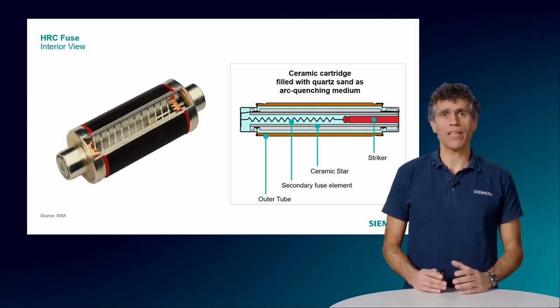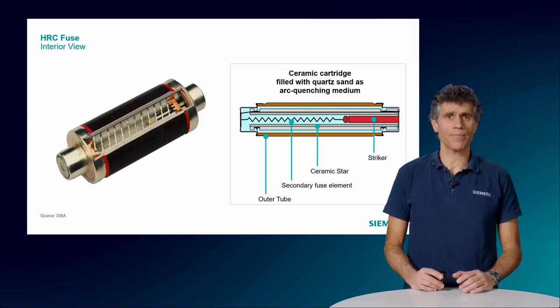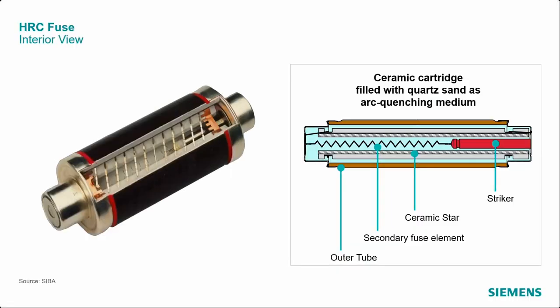The metal wire usually has some shapes that narrow the strip and are engineered to break at the desired currents and time. The wire is wound on a ceramic star with quartz sand, which is used as a quenching medium that melts into glass when the arc forms, which helps to isolate it. Optionally, some fuses are provided with a strike pin that visually shows that the fuse is no longer usable. That pin is usually also connected to a contact that warns that the fuse has tripped and must be replaced, or to initiate further actions such as activating an alarm, isolating the faulted circuit, or even switching to a backup power source.